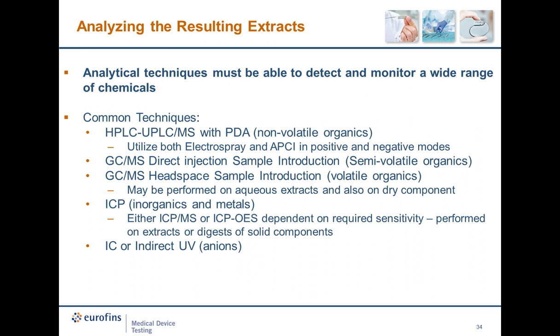After the extraction is complete, the next step is evaluating the extracts generated. A variety of techniques should be used so that extractables big to small and volatile to non-volatile can all be detected. This slide provides a framework for the different techniques that the Eurofins medical device team typically recommends based on the extraction and device to provide a complete extractables profile.